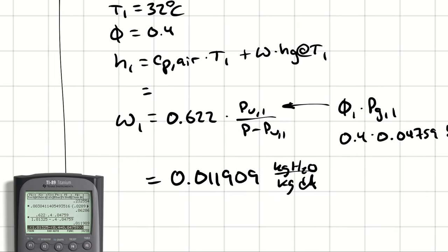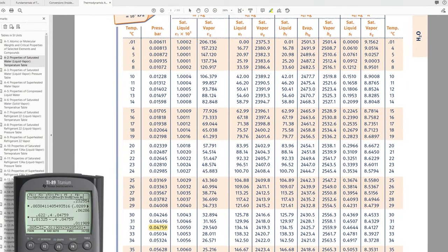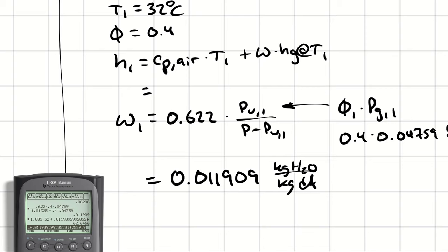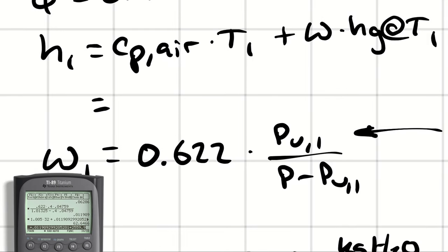Now that I have the humidity ratio, I can calculate h1: 1.005 times T1 in Celsius plus omega1 times h-g at 32°C. From steam tables, h-g at 32°C is 2559.9 kilojoules per kilogram. So h1 = 1.005 times 32 plus 0.01191 times 2559.9 = 62.65 kilojoules per kilogram of dry air. Compare that to 63 from the chart — that's the accuracy we get from hand calculations.